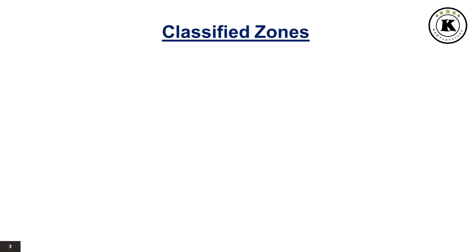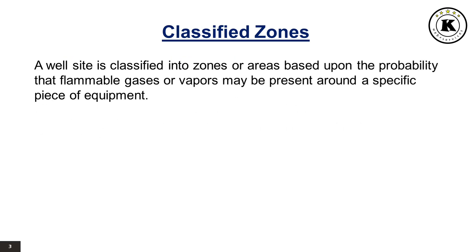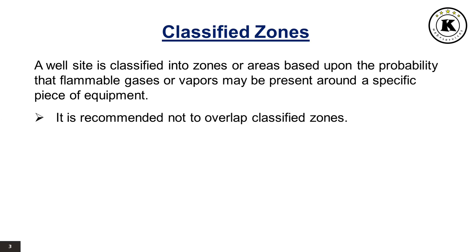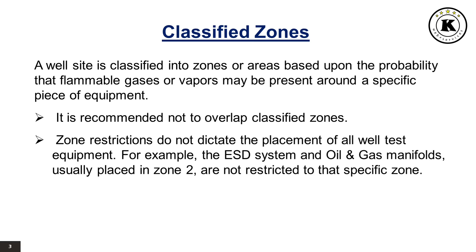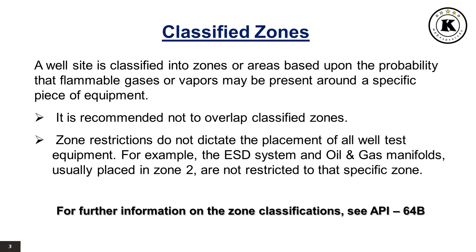A well site is classified into zones or areas based upon the probability that flammable gases or vapors may be present around a specific piece of equipment. It is recommended not to overlap classified zones. Zone restrictions do not dictate the placement of all well test equipment. For example, the ESD system and oil and gas manifolds, usually placed in Zone 2, are not restricted to that specific zone. For further information on zone classifications, see API 64B.